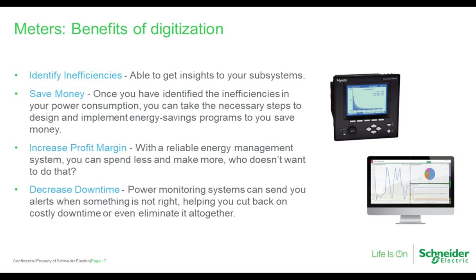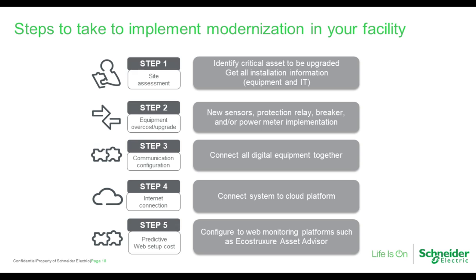Not always can we do something about them, but we can also look at what kind of power is coming into our facility so that we can manage that. And if we have to put in either capacitors, or other devices that help us to smooth out the harmonics and other issues that might be coming down the line. Often there's facilities maybe next door that are providing bad feedback into the system and causing sags and swells within the system as they turn on equipment, which affects our systems. So with power monitoring, we can look at that and see what's happening and get a better clue of what our system looks like, and also what we can do to help improve that system so that we have a much more reliable and safe system at that point. So these are some of the benefits of using meters to get digital information back to our system.